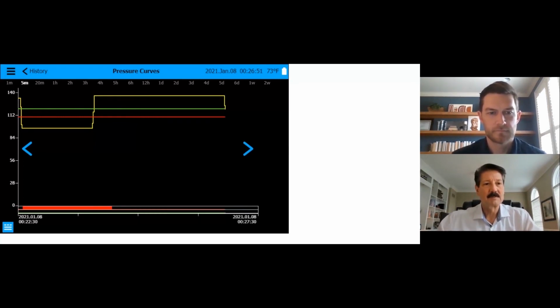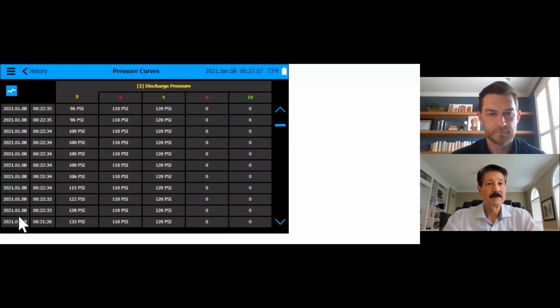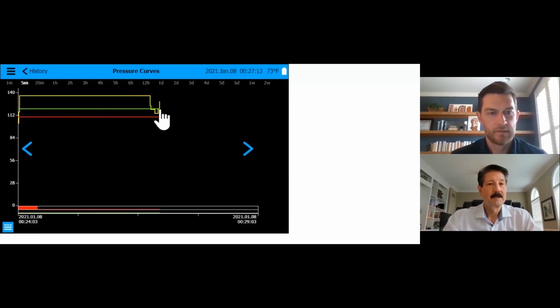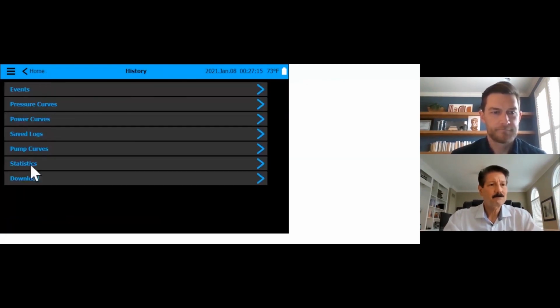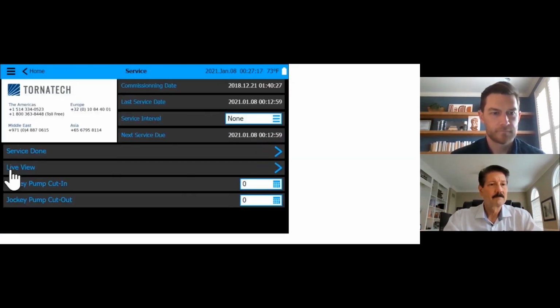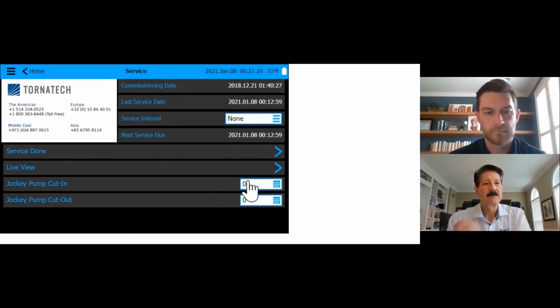and the pressure drops below, but it doesn't go all the way to the cut in, and it increases. It's really the jockey pump doing its job. Right. That's really what we're talking about there. And it makes it easy. But it's nicer to put it in because you will have the cut in, cut out of a jockey. So why not just input it? It increases the accuracy, but it'll do it automatically. Sure. But everything else is the same.